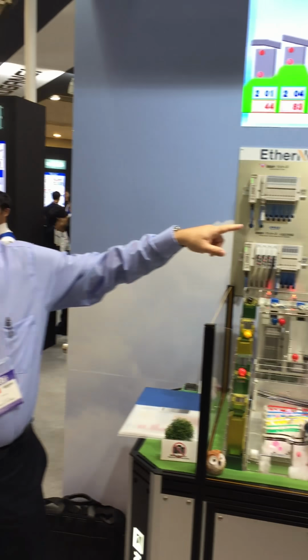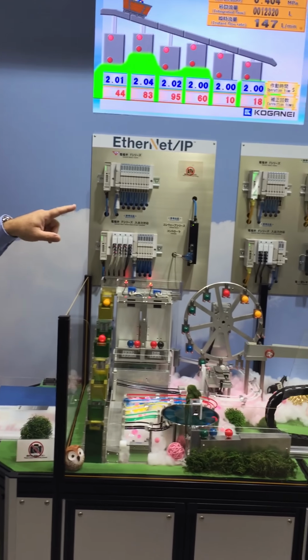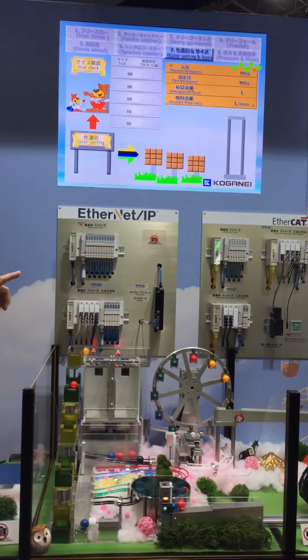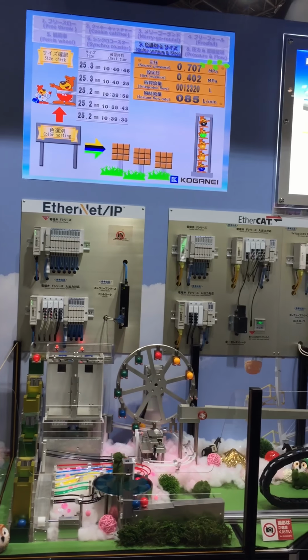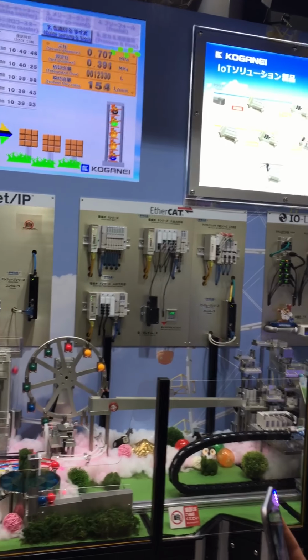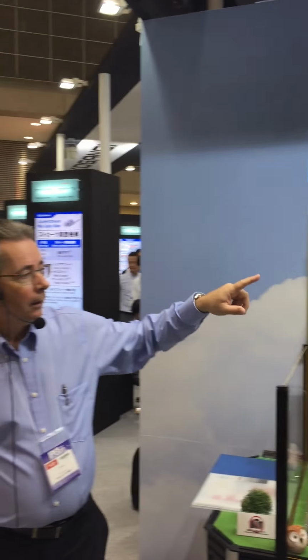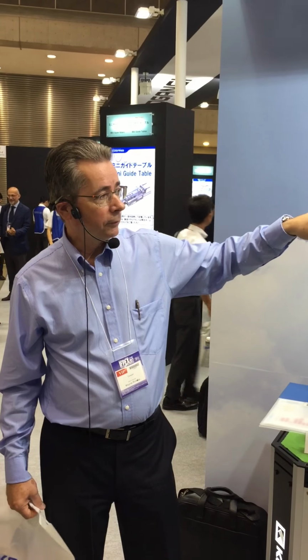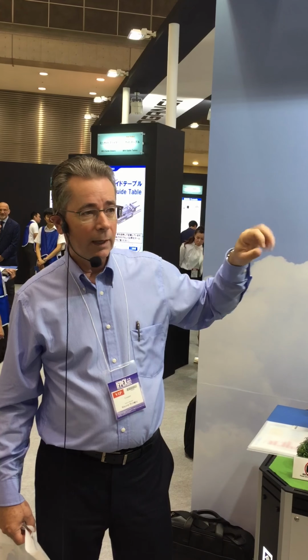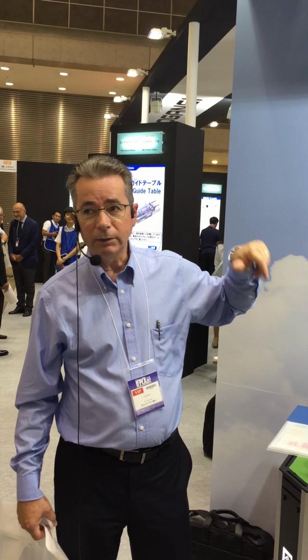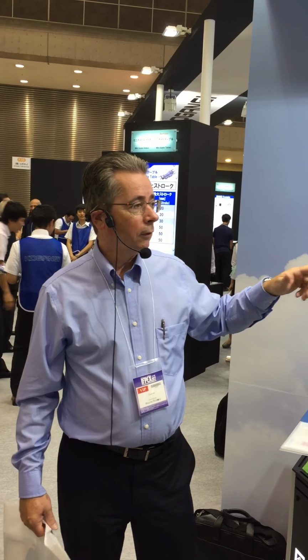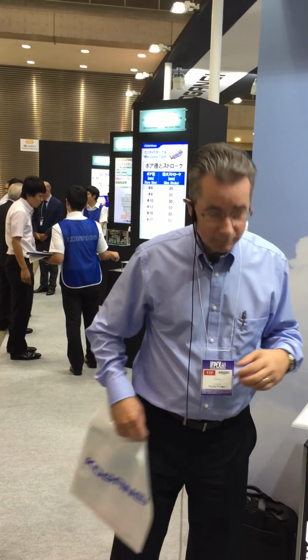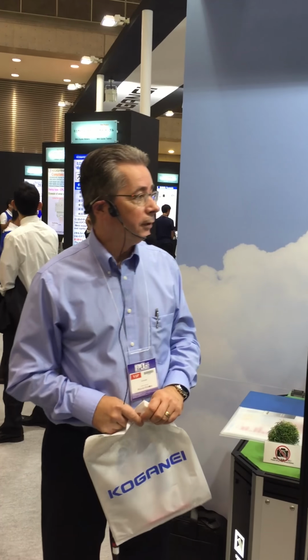There's an adapter on the valve bank that converts the 25 pin inputs and outputs to the IO-Link master. What SMC and Festo are doing now is they're supplying the actual valve block with an M8 connector, and the IO-Link interface is built into the block. So that's what Koganei is working on, and they've told us that maybe by next year they might have a system where they would be doing the same thing.